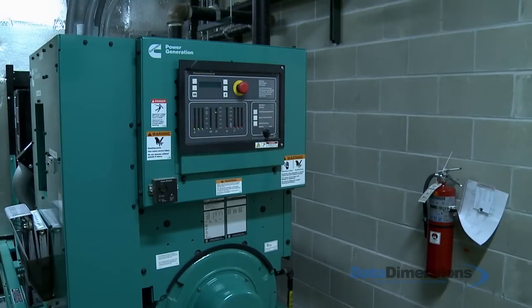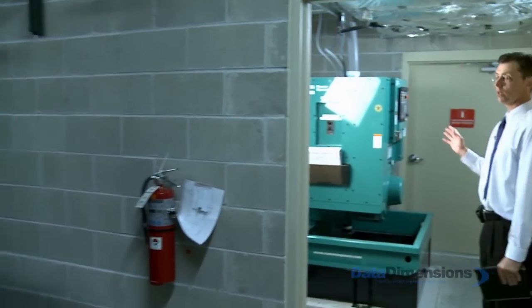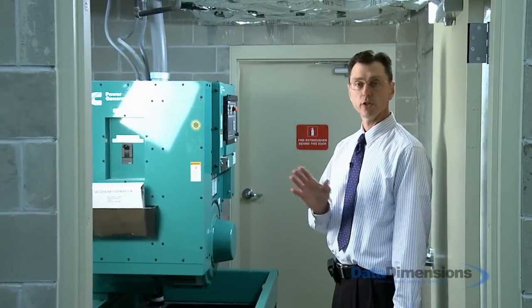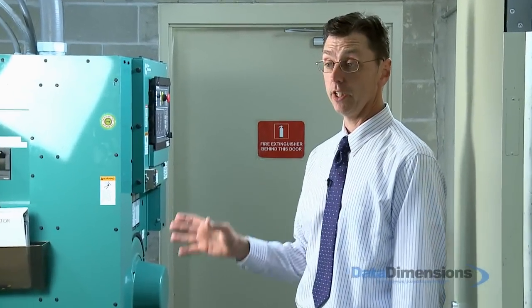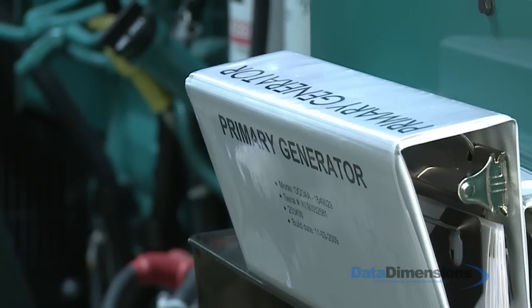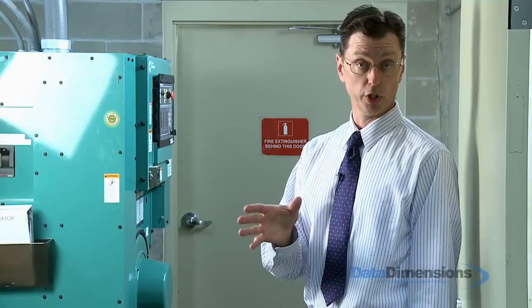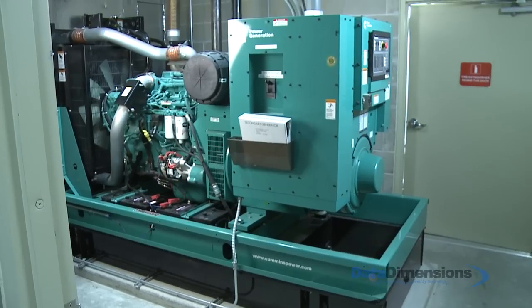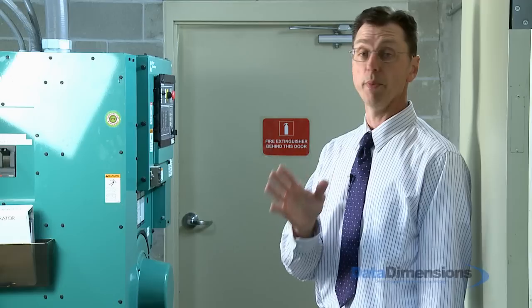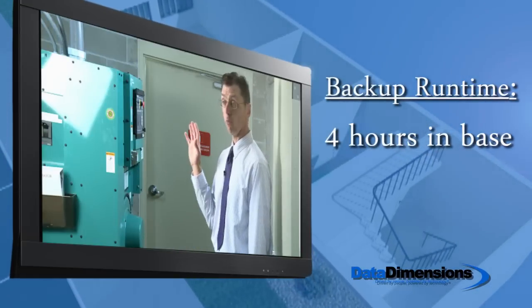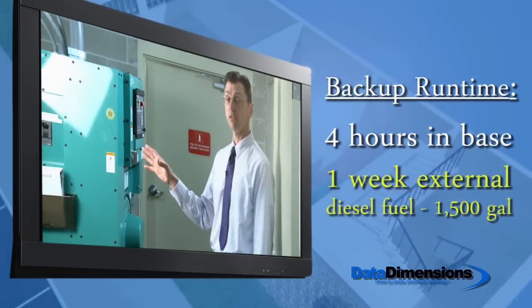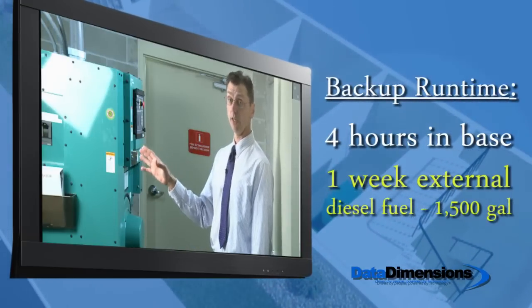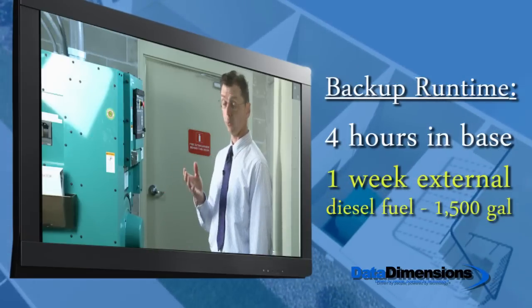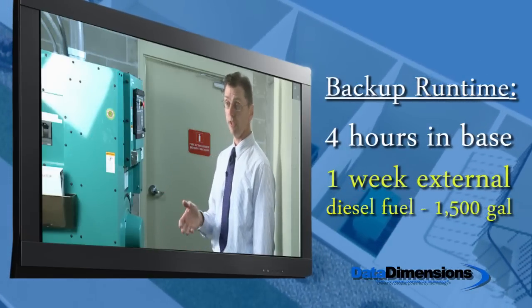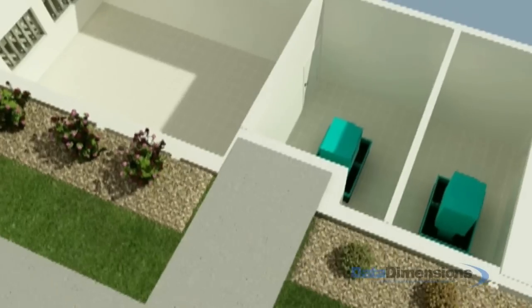We're now in the basement of the facility where we have two 250 kilowatt generators. These are set up in a lead lag functionality where one operates as the primary, kicking in after 10 seconds of a loss of utility power. The second will then fire online if the first fails within a minute and a half. We have 4 hours of runtime in the base of each unit. We have 1 week of runtime and 1,500 gallons of diesel fuel externally to the building. We also have contracts with vendors to resupply us with diesel fuel in the event of a major catastrophe.